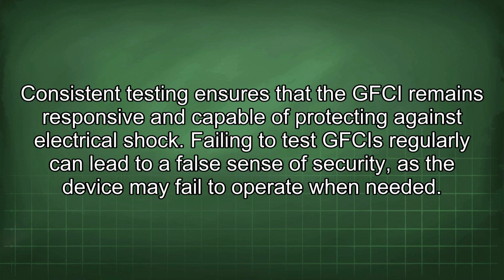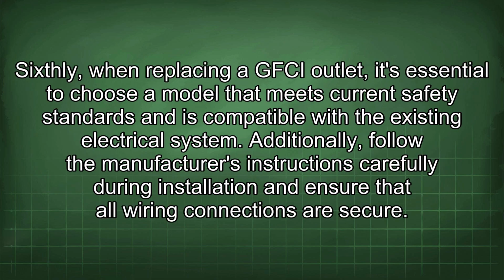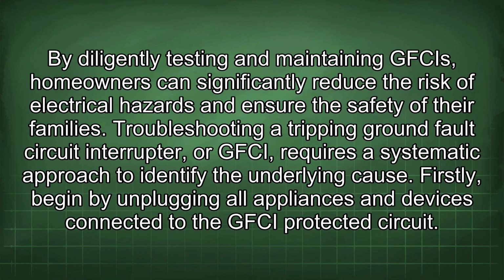Failing to test GFCIs regularly can lead to a false sense of security, as the device may fail to operate when needed. Sixthly, when replacing a GFCI outlet, it's essential to choose a model that meets current safety standards and is compatible with the existing electrical system. Additionally, follow the manufacturer's instructions carefully during installation and ensure that all wiring connections are secure.